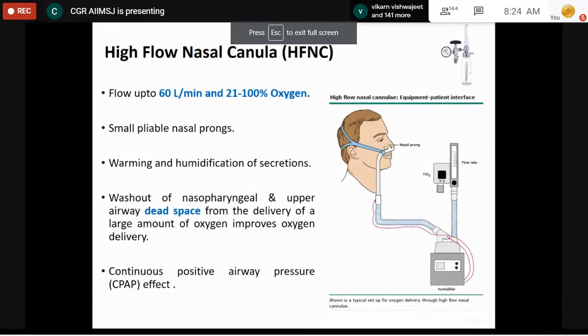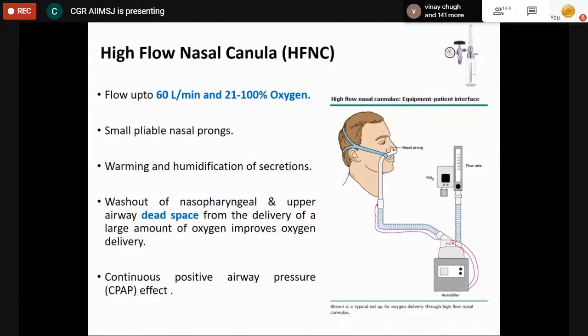Obviously, when you are giving oxygen at such a high rate, it may produce dryness, which may cause discomfort to the patient. So it has to be humidified and heated. The chamber humidifier attached will heat up the air passing through it and humidify it so that the patient is not discomforted, there is no crusting, and there is no drying of secretions. And when the flows are very high, it tends to produce a CPAP effect, so it helps in recruitment of alveoli and washing out of carbon dioxide as well.